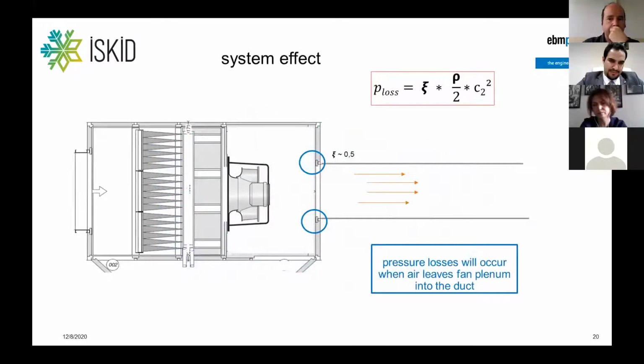So this could be, let's say, one effect when you use a plenum fan. If you have a plenum fan, you have filters and dampers in the air handling unit, and if you blow, for example, the air from the plenum directly into a duct system, you will create some losses, and this is expressed by this formula, and it goes in square with the air velocity. For a sharp edge, there's the zeta factor 0.5. So you multiply this with that, and the higher the airflow in the duct, the higher the losses will be. So this is a part of this a fan manufacturer can never cover in the selection. So you have to be aware of what is behind the metrics.